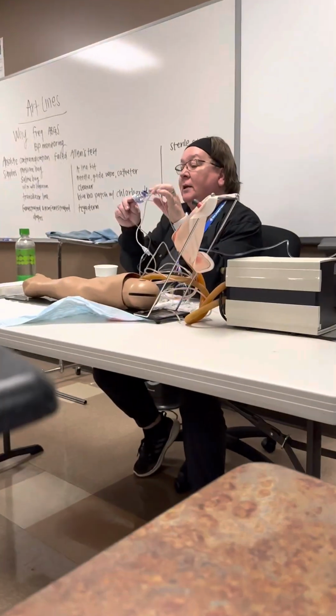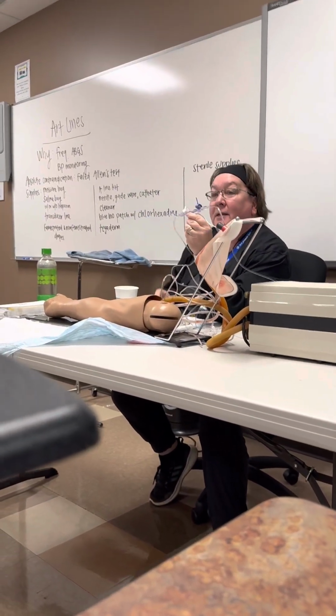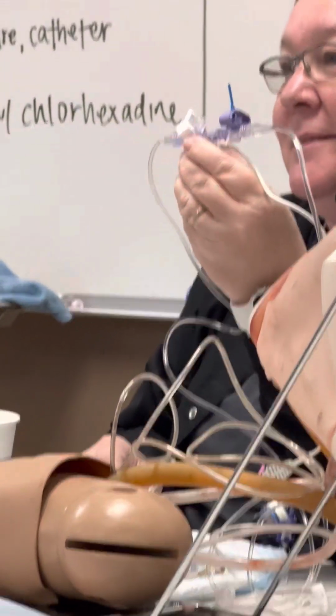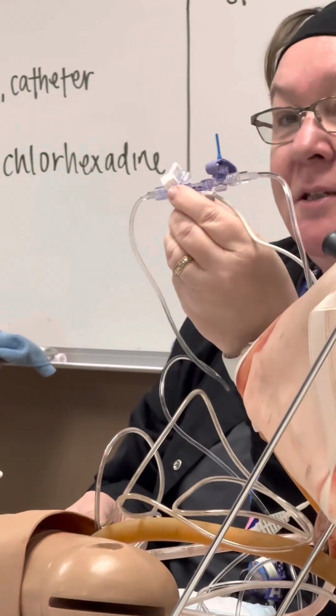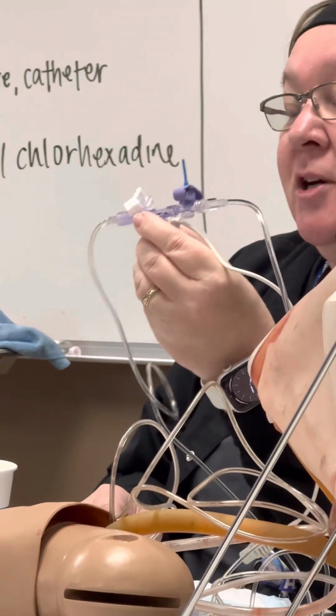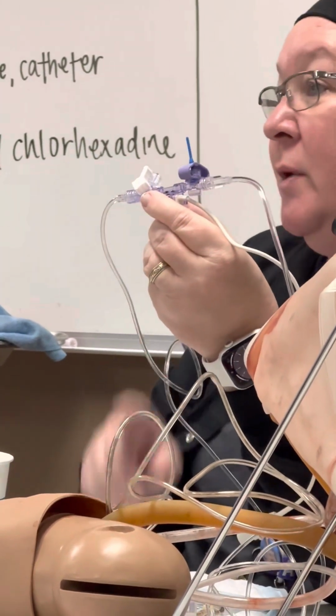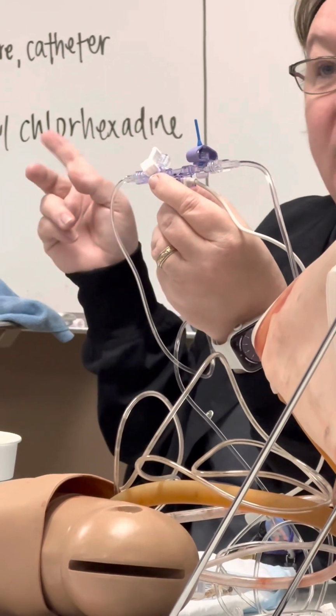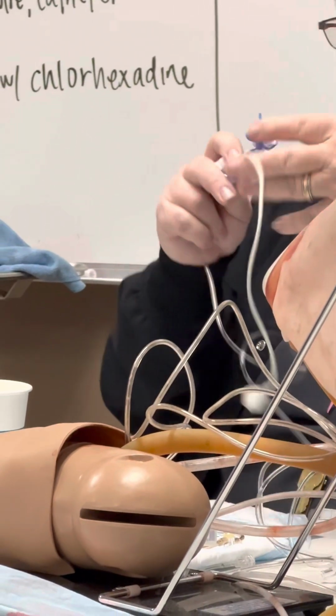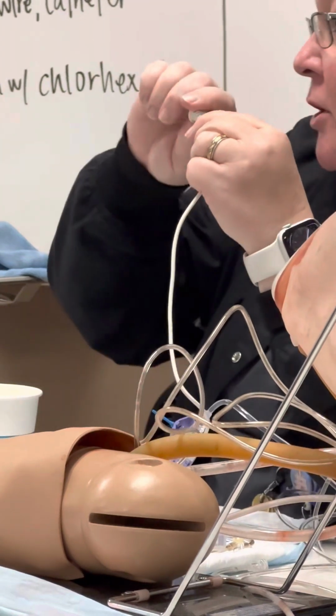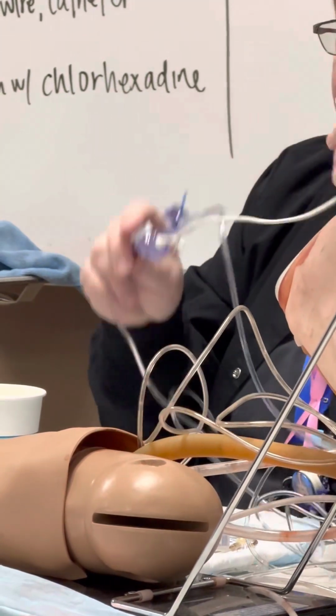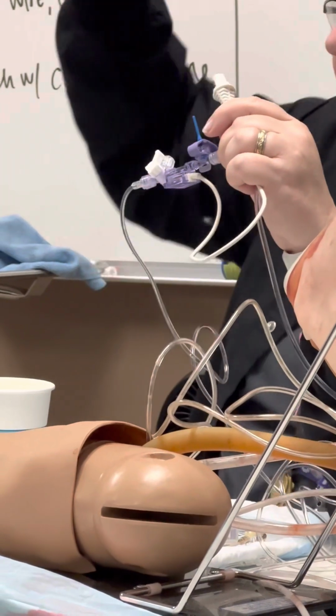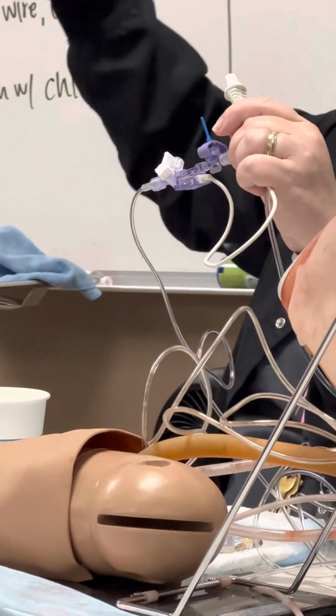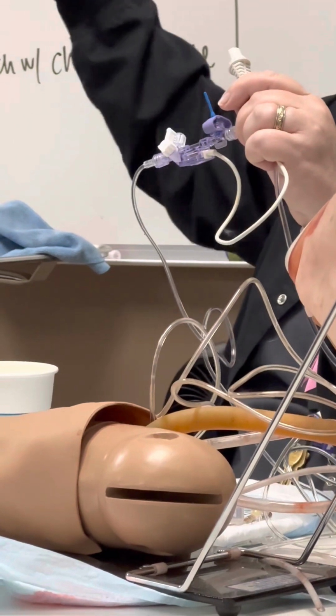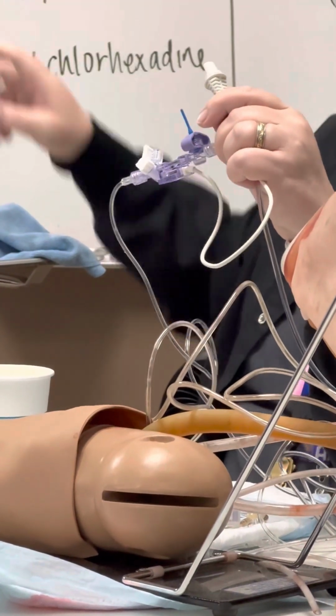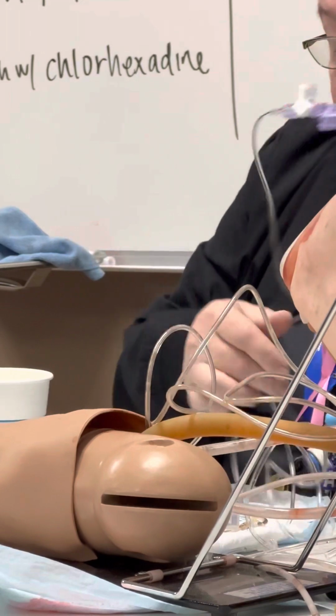So this part here is the transducer. Come on, guys, we'll play more later. This part here is the transducer. The purpose of the transducer is to convert the pressure to a waveform reading on the monitor. So there's a little port here. This would hook to the port from the monitor. And once it's inside the patient and working, you would get your waveform. It looks like a pulse oximetry waveform. It should be nice and have that nice little dicrotic notch in it. You guys have seen them on the monitors. But for right now, we're just gonna do this.